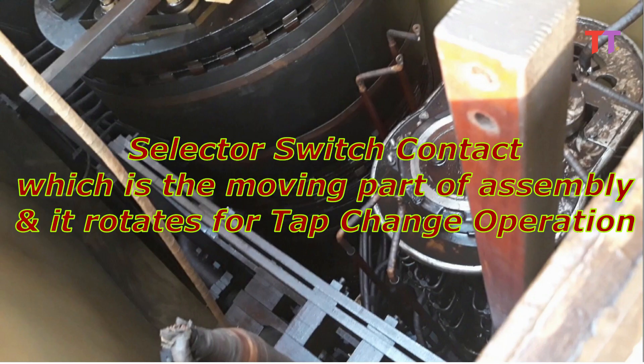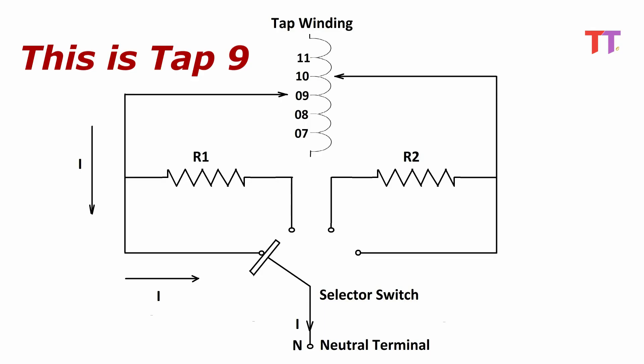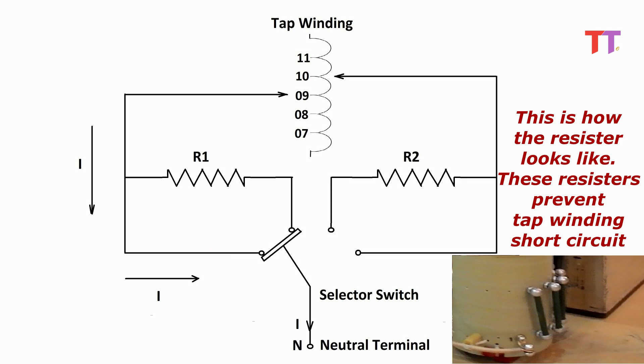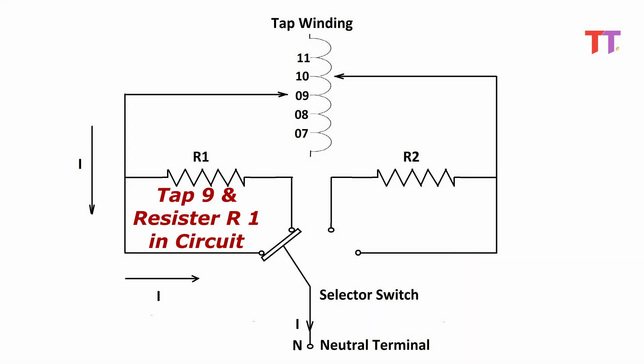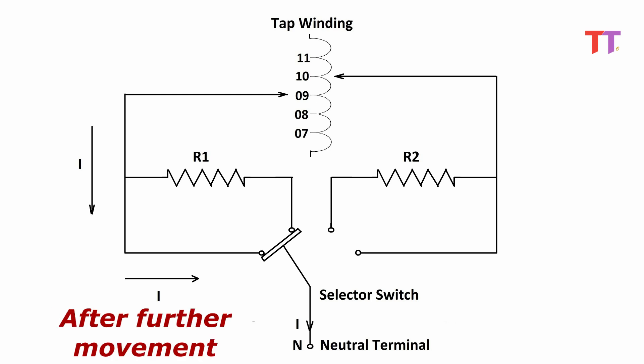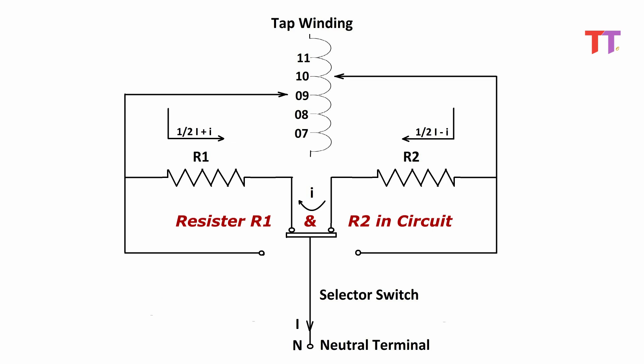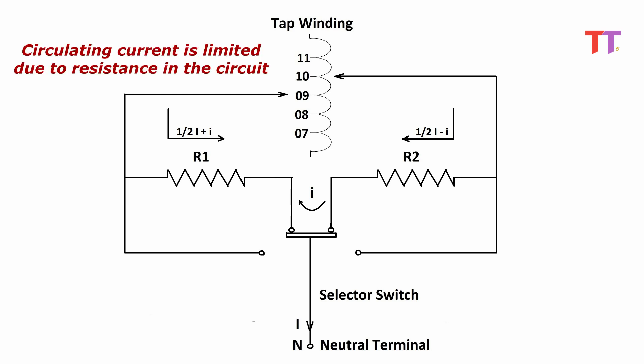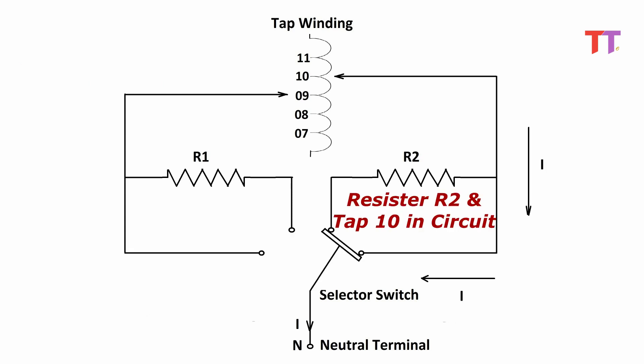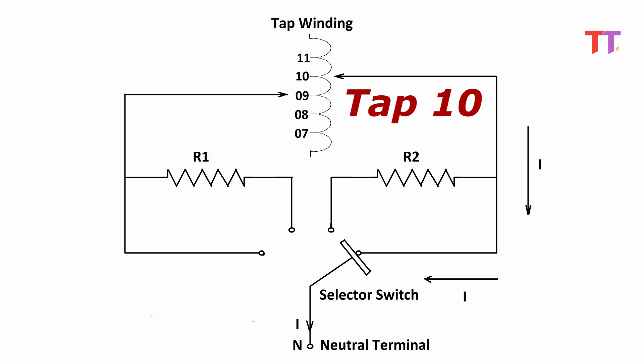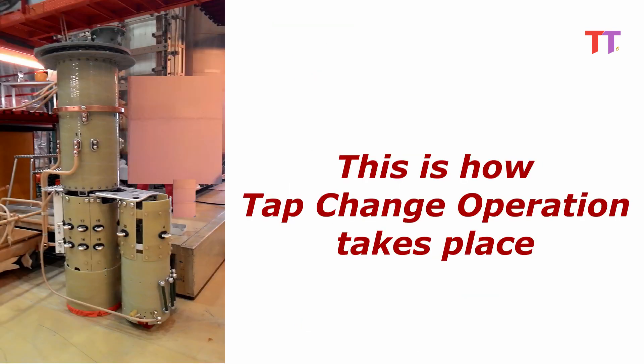The selector switch contact, which is the moving part of the assembly, rotates for tap change operation. Starting at tap 9, while moving, resistor R1 comes into circuit. These resistors prevent tap winding short circuit. Now there is tap 9 and resistor R1 in circuit, hence current flows through the tap winding, which is the obvious low-resistance path. After further movement, resistors R1 and R2 come into circuit, so a small circulating current flows through this closed path, limited by the resistance. Now there is resistor R2 and tap 10 in the circuit — current flows through tap 10, which is a low-resistance path. Finally, the selector switch moves to tap 10. This is how the tap change operation takes place.